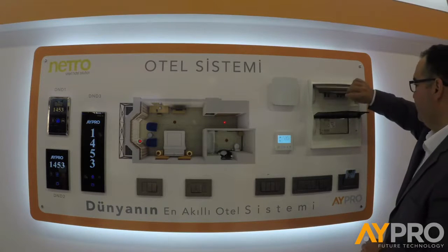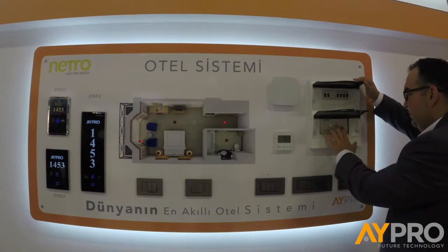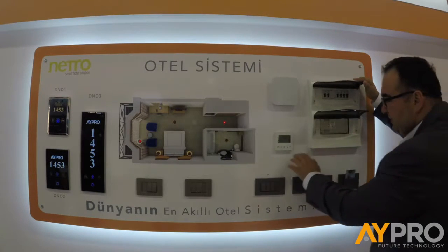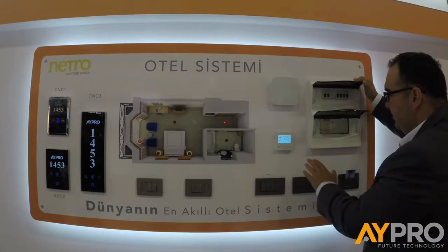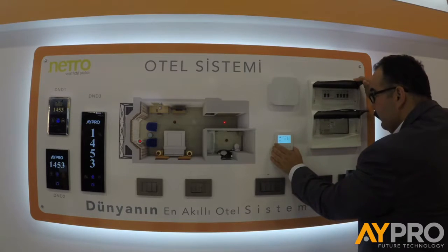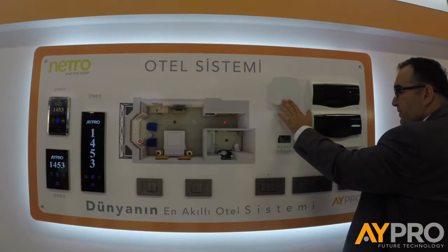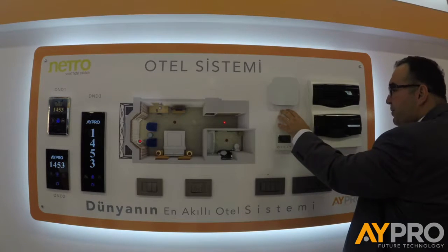For the panel distribution board, you have standard fuses here, and you can use any brand, and you just use our hotel integrated system, and this can be connected to the thermostat directly. So in one room, we have one room controller on the panel, and you have one thermostat here. And the communication is very easy, because we don't need any Cat5 cables or any bus cables through the hotel room. We just have the gateway here, and the gateway stays in the corridor, and this gateway can talk with 10 up to 15 different rooms.